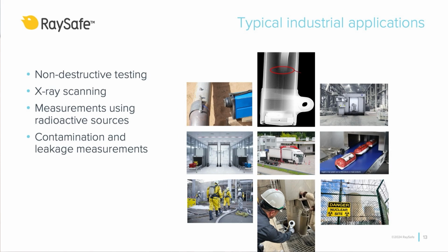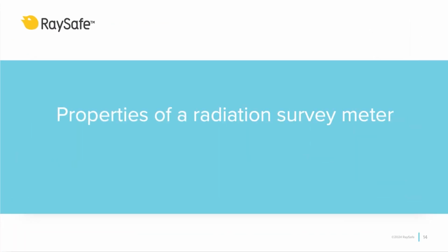I guess most people understand there are X-rays in a hospital, but X-rays are also used in the non-medical field, and it is as important to make similar measurements there. Some examples of non-medical X-ray usage are non-destructive testing for detection of defects in material, weldings, and so on. There are different types of scanners in customs, airport, and border controls. Radioactive sources can be used for level control in tanks. It is common in food and pharma to look for contamination in the final product.